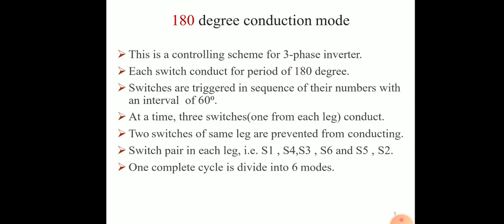Switches are triggered in sequence of their number with an interval of 60 degrees. T1 conducts, then T2 is fired after 60 degrees of T1, T3 fired after 60 degrees of T2, T4 fired after 60 degrees of T3, T5 fired after 60 degrees of T4, and T6 fired after 60 degrees of T5. At the same time, 3 switches conduct — 1 from the positive group and 2 from the negative group, or 2 from the positive group and 1 from the negative group. Two switches of the same leg are prevented from conducting simultaneously because that would produce a short circuit across the supply. Switch pairs in each leg are S1 and S4, S3 and S6, S5 and S2.